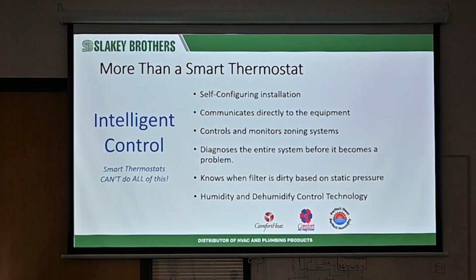Again, it's a really, really smart controller. It does everything for you. It self-configures and helps you control extra stuff like, say, your humidifier. For our variable speed equipment, it helps you dehumidify a house, or for wintertime, it'll help you use the humidity controls in it to control a humidifier. So you don't have to add an extra control in there. If you're going into a home that really needs extra dehumidification, you can do this without installing a separate dehumidifier for the house itself, especially if you have a variable speed unit, because it can use a lower speed of a compressor with lower airflow to get a really cold coil and remove moisture out of the air.